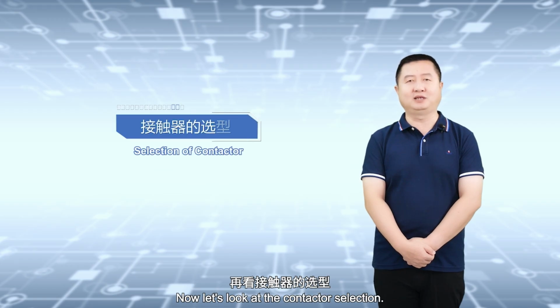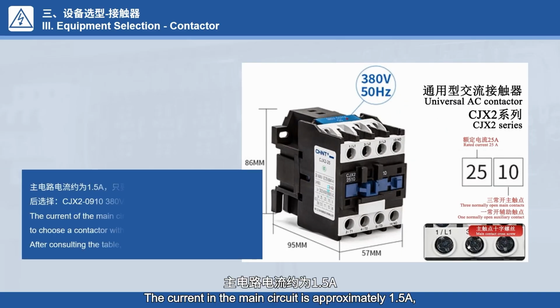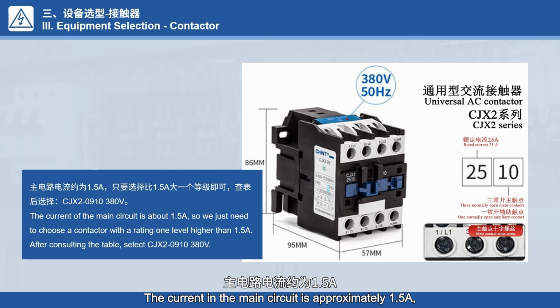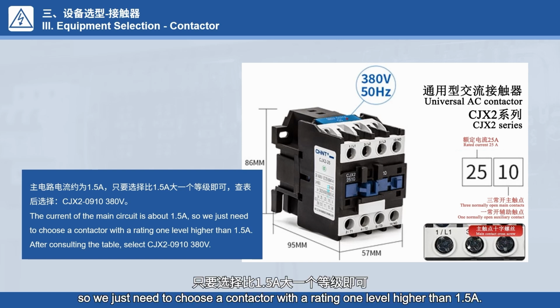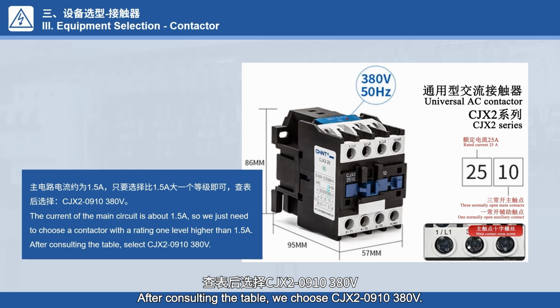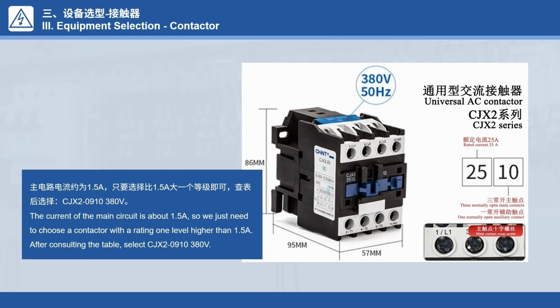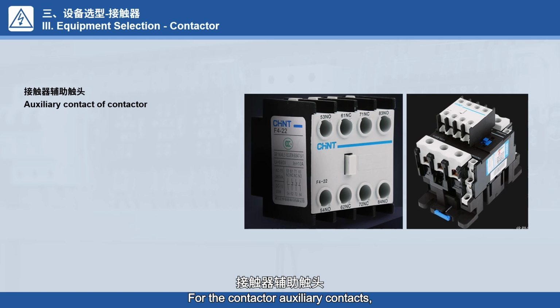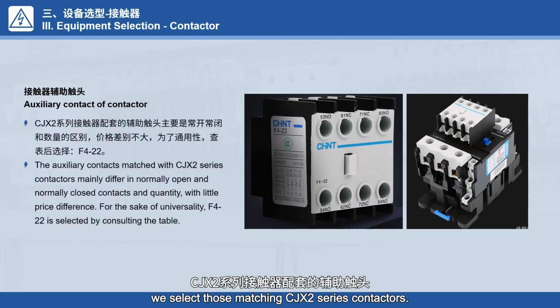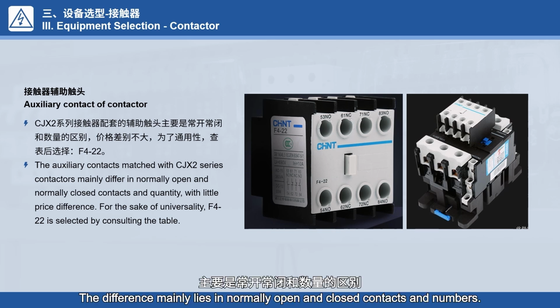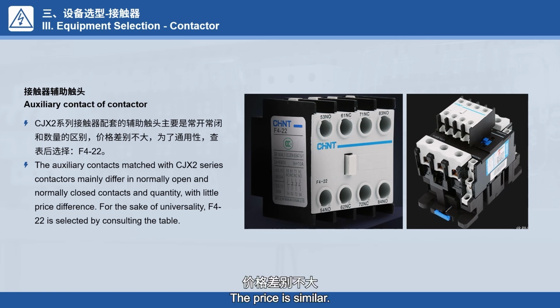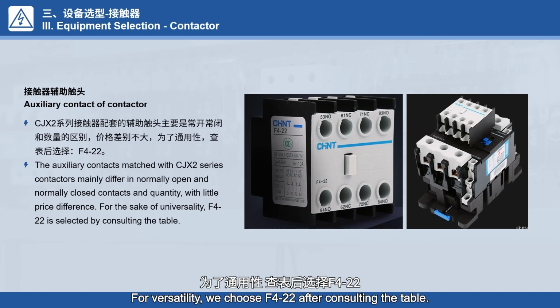Now let's look at the contactor selection. The current in the main circuit is approximately 1.5 amperes, so we just need to choose a contactor with a rating one level higher than 1.5 amperes. After consulting the table, we chose CJX2-0910 380 volts. For the contactor auxiliary contacts, we select those matching CJX2 series contactors. The difference mainly lies in normally open and closed contacts and numbers. The price is similar. For versatility, we choose F4-22 after consulting the table.